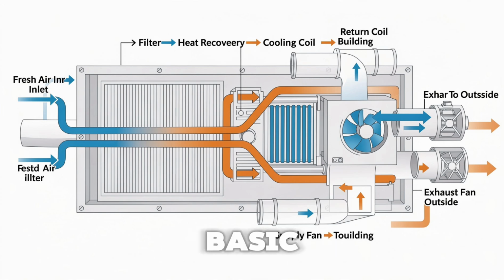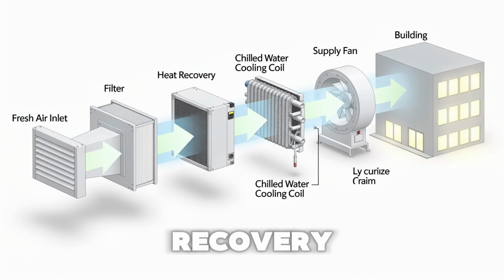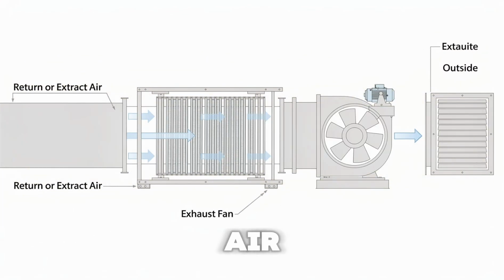So remember the basic FAHU airflow. Fresh air inlet to filter, to heat recovery, to cooling coil, to supply fan, to building. And on the exhaust side, return or extract air, to heat recovery, to exhaust fan, to outside.